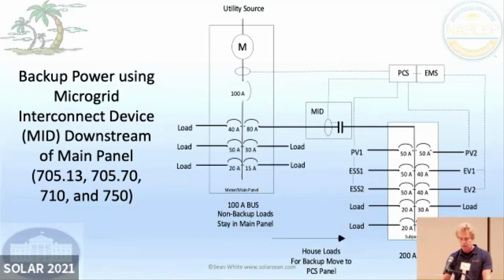We've got pretty much the same thing. And so this is power control systems. And we also have an energy management system, could be the same computer. We've got a microgrid interconnect device here, checking the current here. Here in Hawaii, you're not allowed to feed the grid. There's already too much solar feeding the grid. It's a small grid. So you have a current transformer or current transducer, a CT, they call it. You're monitoring right by the meter just to make sure that no electricity goes backwards. When it starts to get close to going backwards, then you start charging the battery or cutting things off and turning on different loads. And they have all kinds of neat stuff. You pump water, you could heat your swimming pool, your hot tub, cool off your freezer extra cold, charge your electric vehicles. This kind of system that we have right here is the future with all this stuff. You know, we've got PV, energy storage, another PV system you installed later.